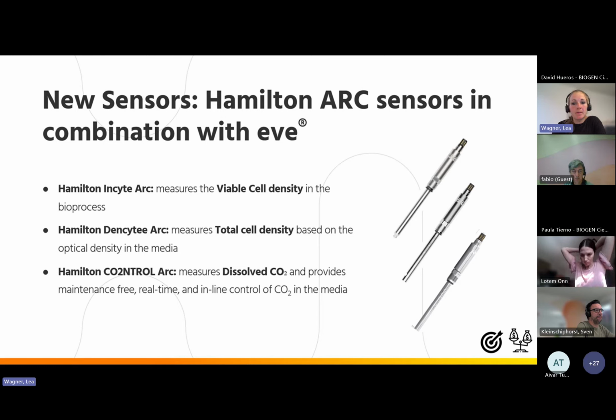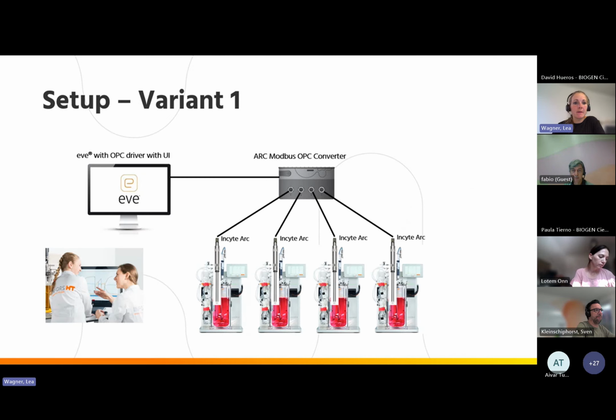There are different ways to set up the sensors with Eve and the device. The first possibility is to have one box. What is needed for this solution is that the customer needs Eve and the OPC driver with UI, and also a so-called ARC Modbus OPC converter, which is a little small box from Hamilton. To this box, up to 4 Hamilton ARC sensors can be connected. So, for example, if the customer has 4 Minifors 2 and wants to have an Incyte ARC in each Minifors, the customer can buy one box and then connect 4 Incyte ARCs to this box.